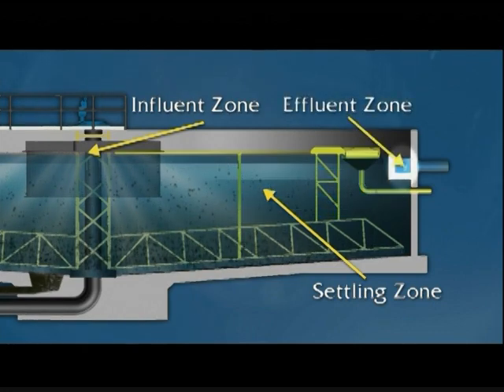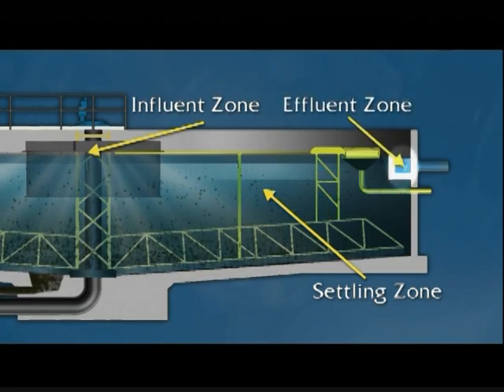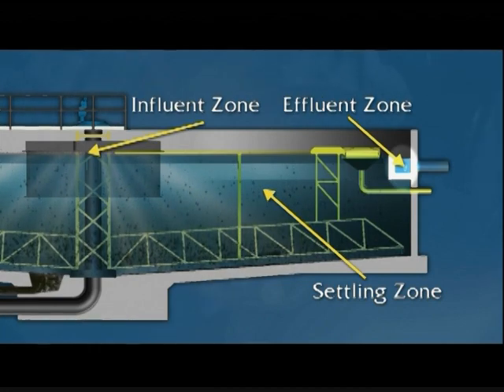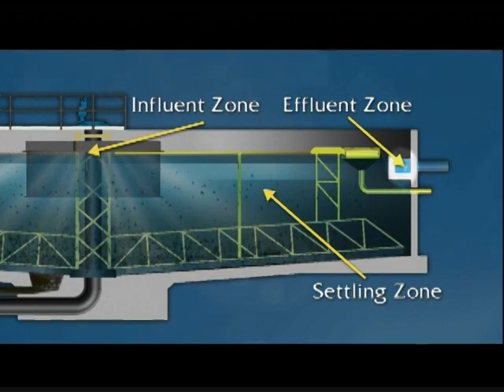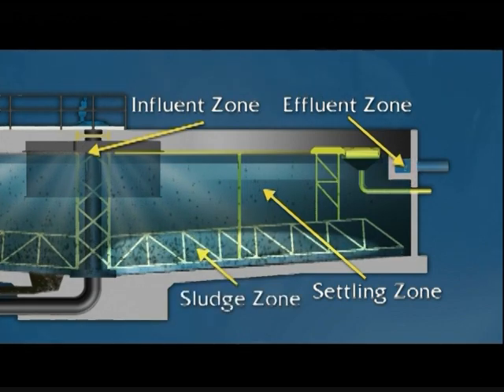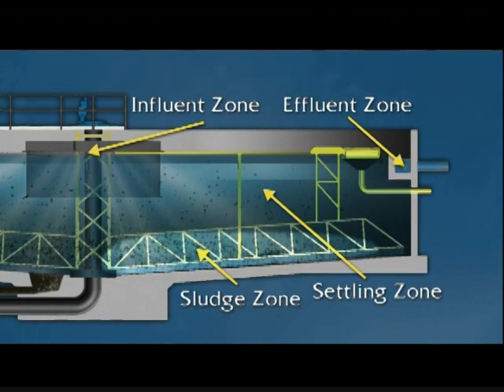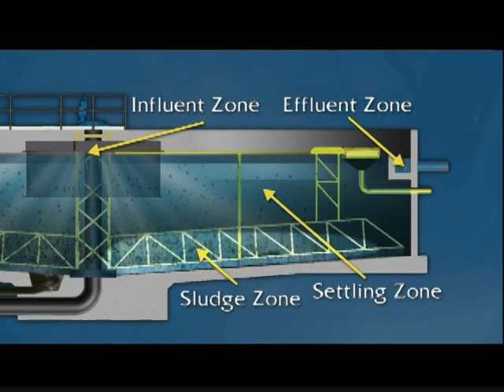Three, the effluent zone provides a smooth transition from the settling zone to the effluent flow area. It's important that currents don't stir up any settled solids and carry them into this area. Four, the final zone is the sludge zone, where settled solids are separated from other particles in the settling zone.